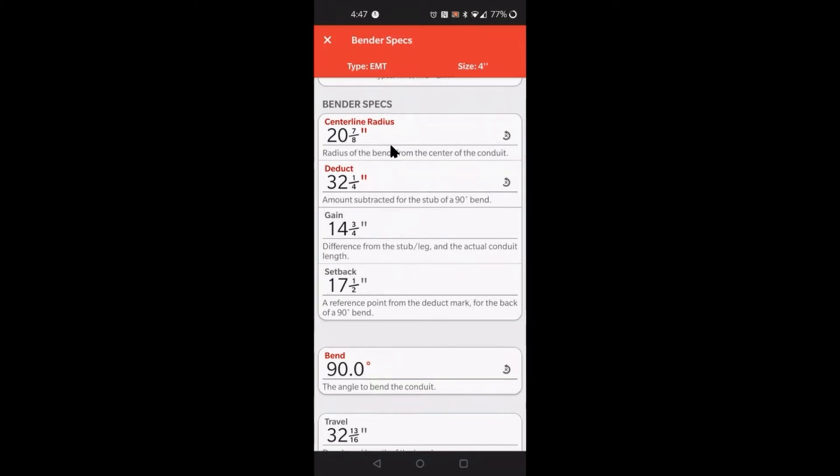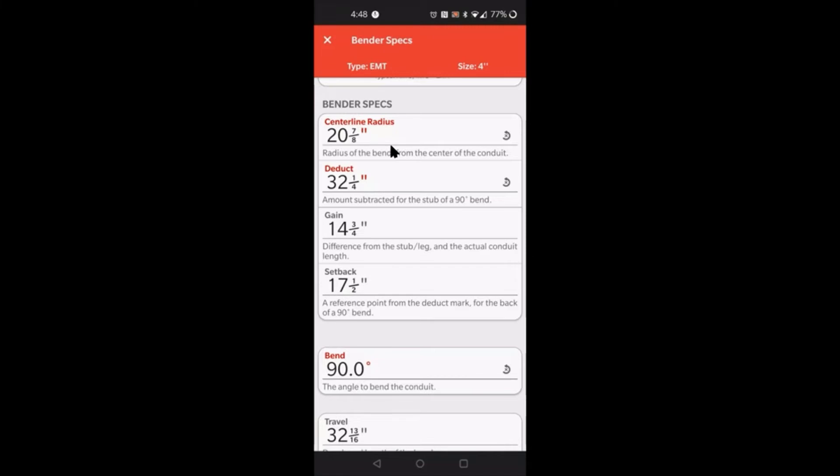It gives you the centerline radius for that 4 inch EMT. What do you use the centerline radius for? You can actually use it mostly when you're doing concentric bends. If you want to know what the first reference conduit radius centerline radius is going to be, it gives you the value right here, 20 and 7/8. Word of advice, I always like to measure my radius myself for my reference conduit, because sometimes every bender is not created equal. The centerline radius value can vary from bender to bender.